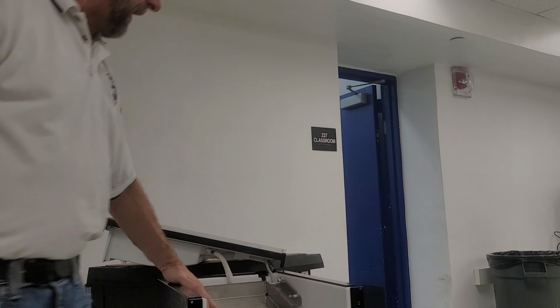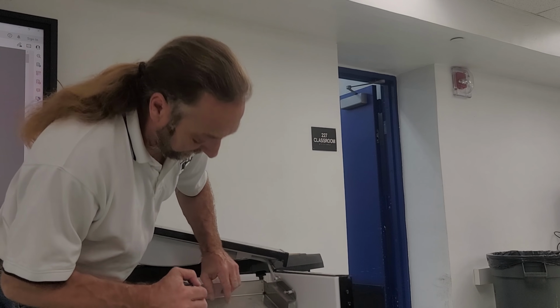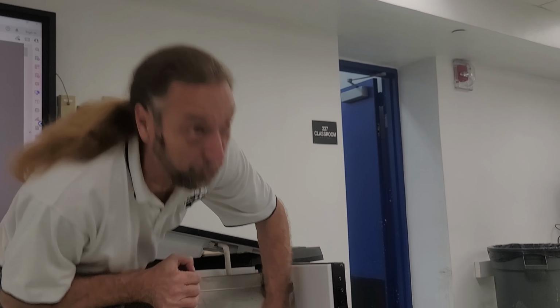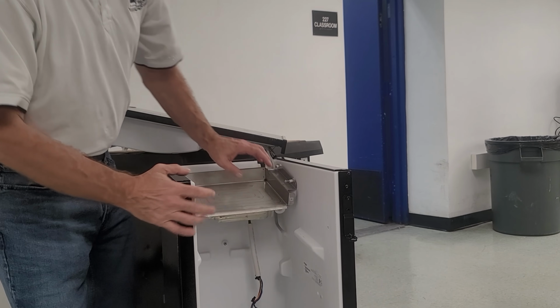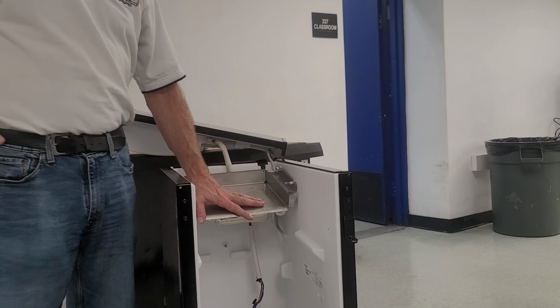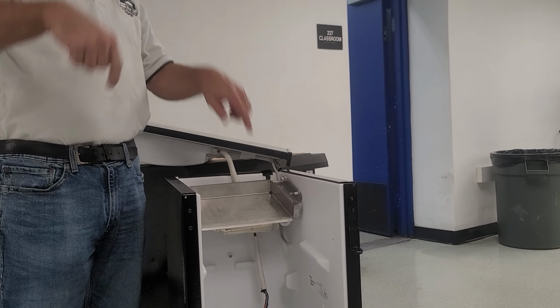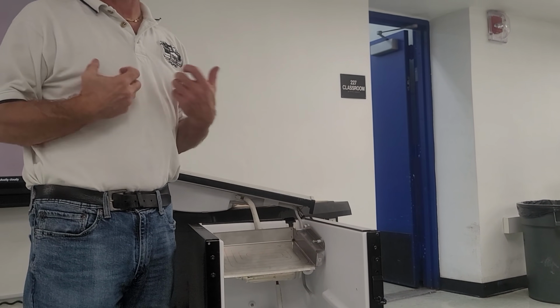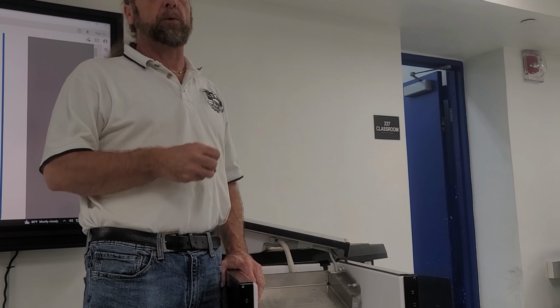So now you can see our evaporator a little better. I'm gonna tilt it back just a little bit, and there's an accumulator down here. As the evaporator is forming ice, and the water now is flowing over the ice, not the evaporator, we're not absorbing as much heat from this evaporator. So what the accumulator does is it traps any liquid refrigerant and prevents that liquid refrigerant from coming back into the compressor and damaging the compressor.